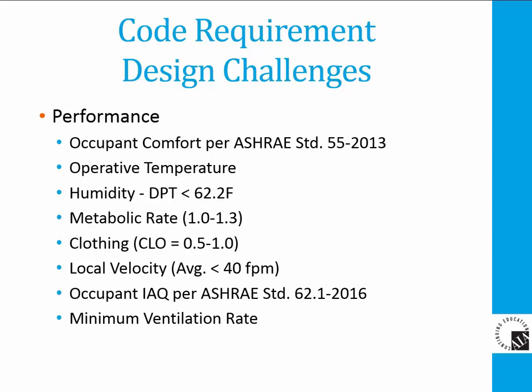For most office spaces, it is assumed that the activity level or metabolic level of occupants will be between sedentary at 1.0 to slight activity levels of less than 1.3. Design adjustments are made to include the clothing insulation levels of occupants with a range from light summer attire, a CLO rate of 0.5, to business attire with a CLO rate of 1.0. Average local velocities in the occupied space must remain below 40 to 50 feet per minute.